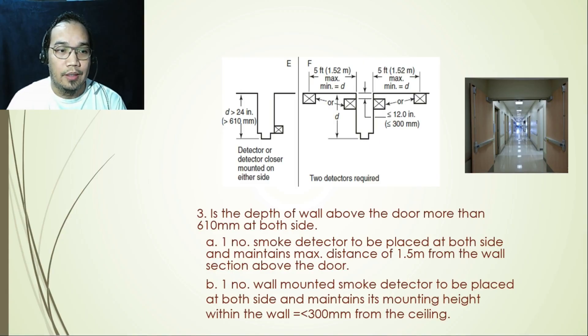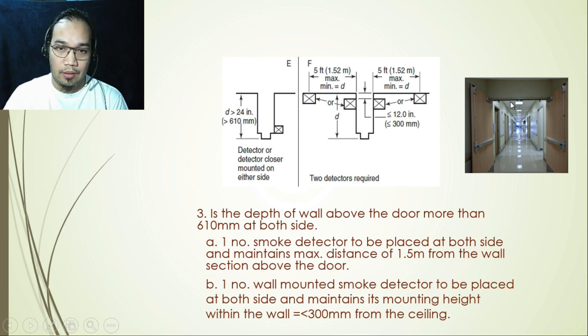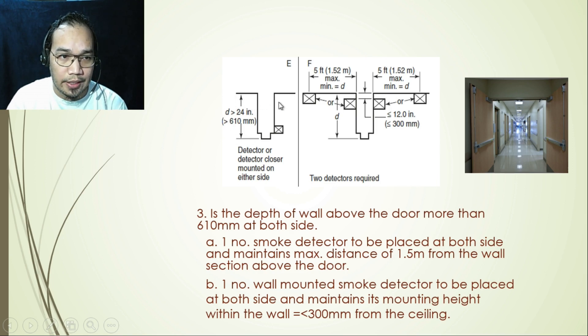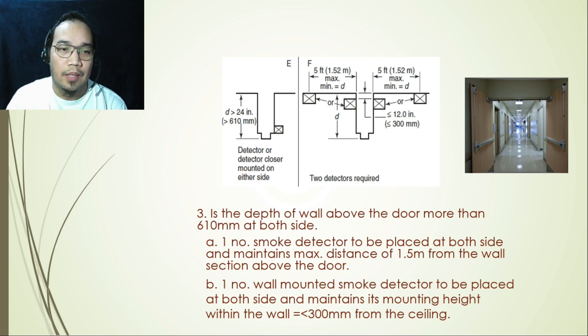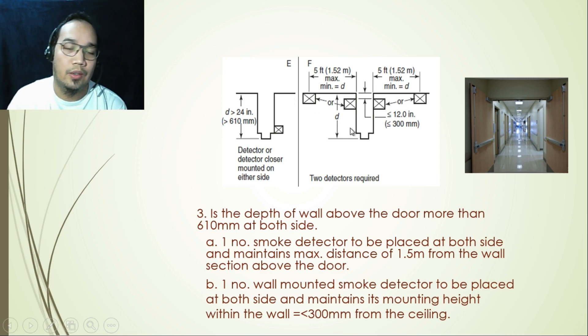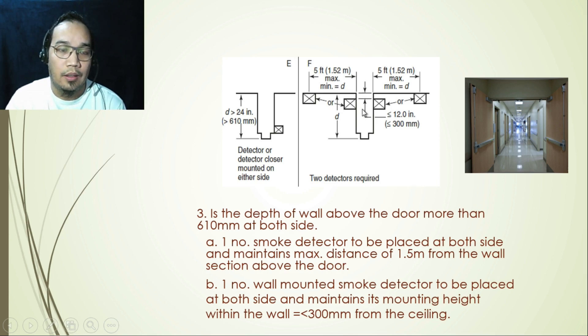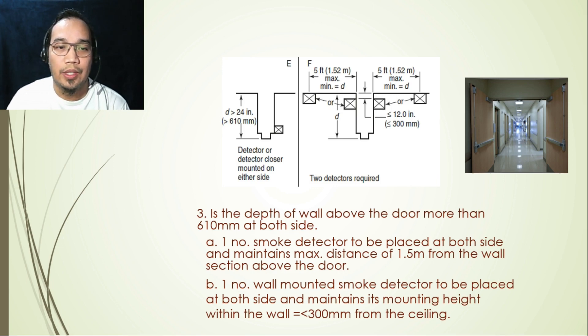The third case is when the depth of the wall above the door is more than 610 mm on both sides. As shown in this illustration, both sides exceed 610 mm. In this situation, there is no option to provide only one detector — two detectors are mandatory, one on each side. For ceiling-mounted detectors, maintain 1.5 meters from the wall above the door; for wall-mounted detectors, maintain a maximum distance of 300 mm or less from the ceiling.